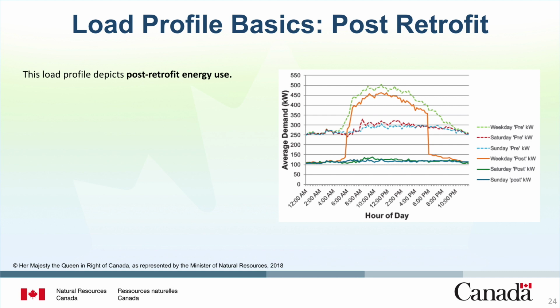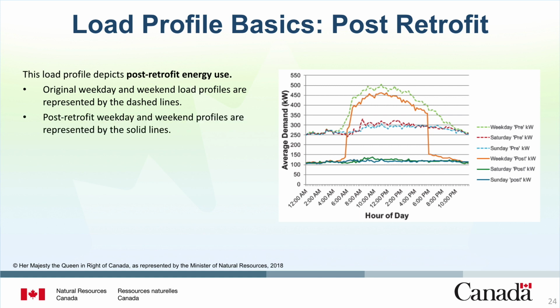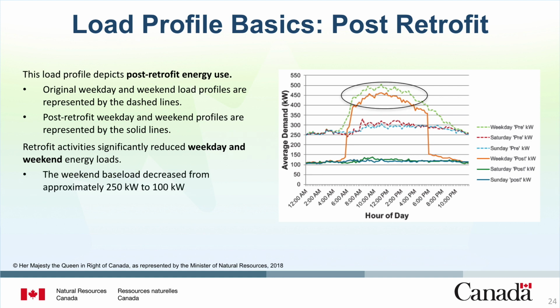Load profiles can also be used to estimate energy savings after a retrofit project has been completed on a building. This load profile depicts post-retrofit energy use. Original weekday and weekend load profiles are represented by the dashed lines. Post-retrofit weekday and weekend profiles are represented by the solid lines. As you can see, retrofit activities significantly reduced weekday and weekend energy loads. The weekend base load decreased from approximately 250 to 100 kilowatts. Peak energy load has also been reduced from approximately 500 to 450 kilowatts.